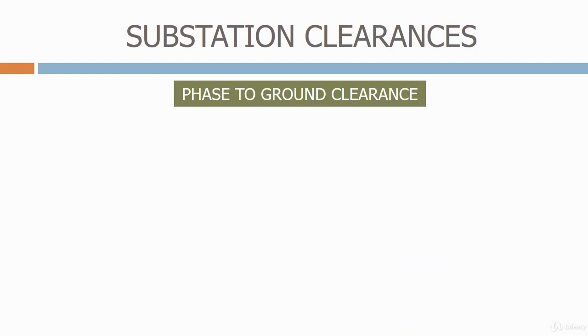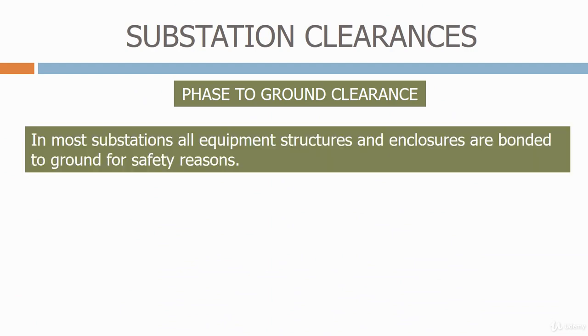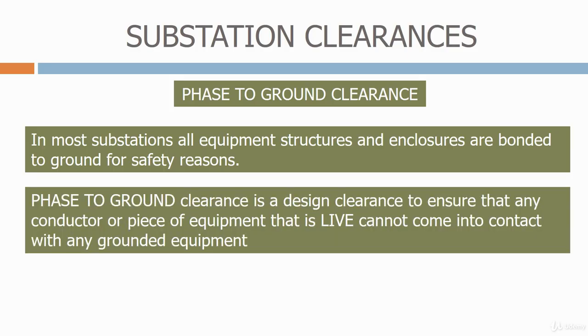Firstly, let's look at the phase-to-ground clearance. In most substations, all equipment structures and enclosures are bonded to ground for safety reasons. Phase-to-ground clearance is a design clearance to ensure that any conductor or piece of equipment that is live cannot come into contact with any grounded equipment.